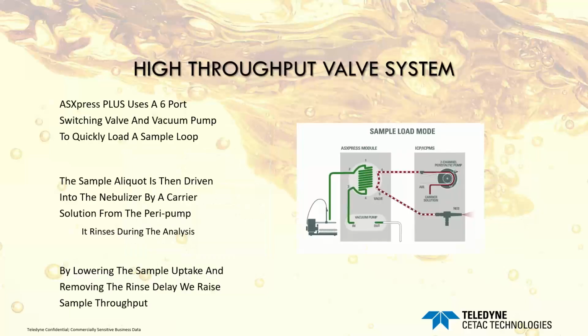Now, the ASXpress Plus is a high throughput valve system. It uses a 6-port switching valve paired with a vacuum pump to quickly load a sample loop. The sample is then driven from the loop into the nebulizer by a carrier solution. And the carrier solution is pushed by the peristaltic pump on the ICP. The system rinses during the analysis. So what does all of this do for you? It lowers the sample uptake time, removes the rinse delay, and raises your sample throughput.